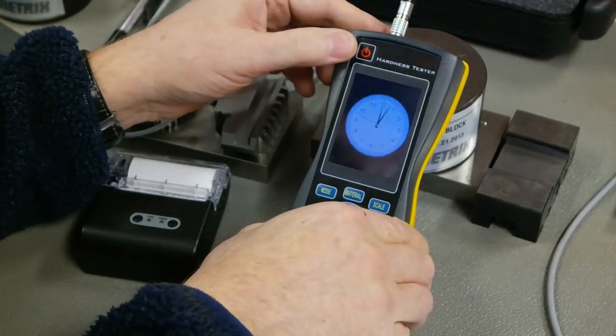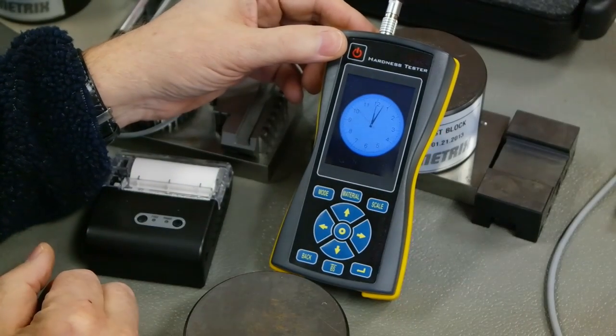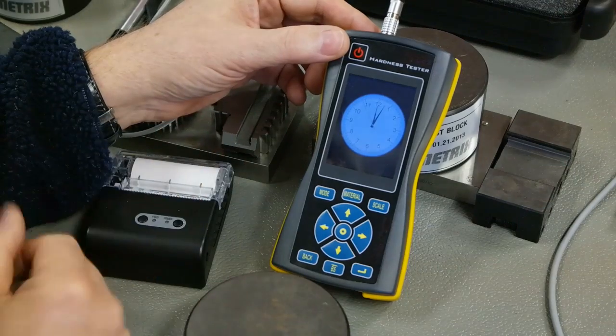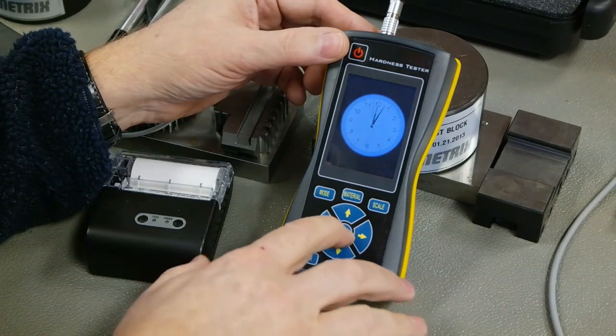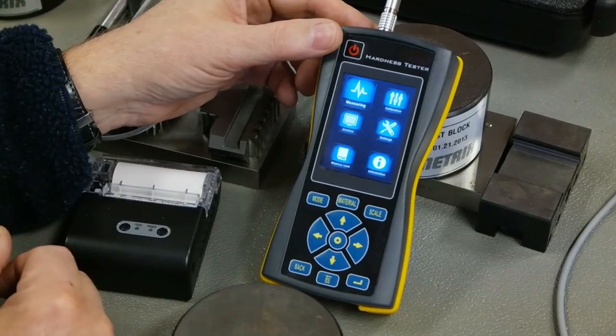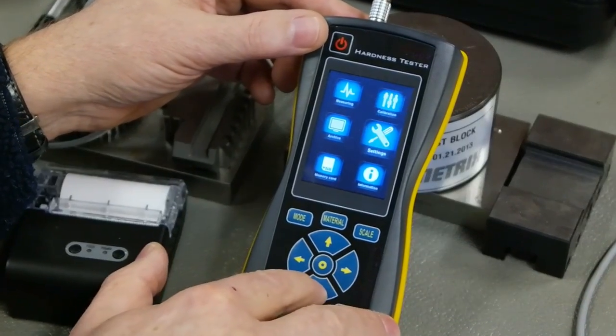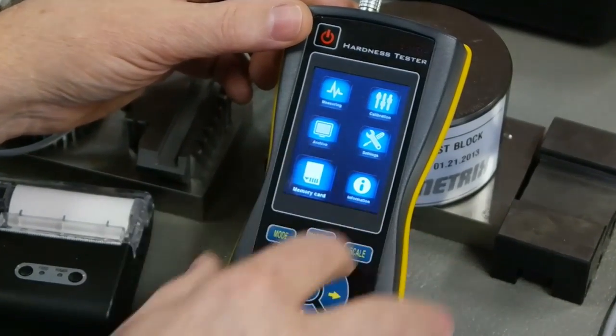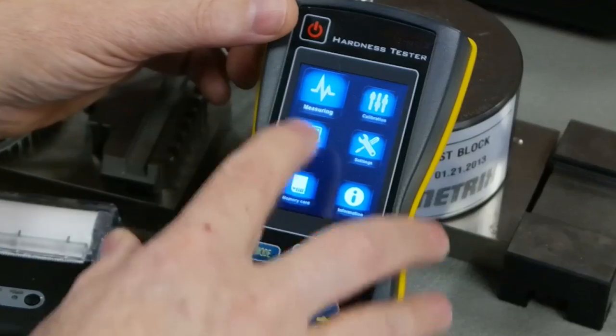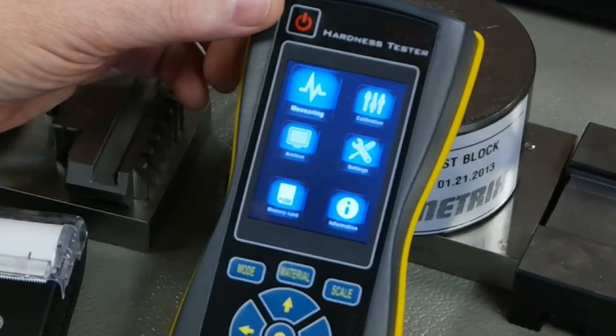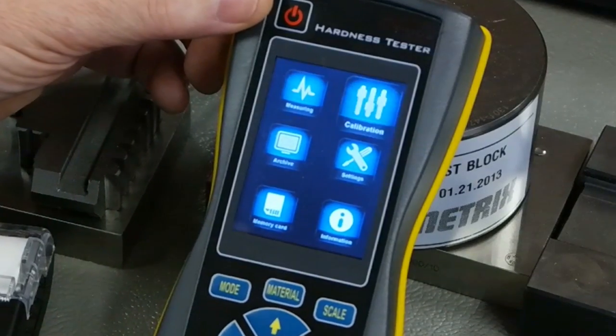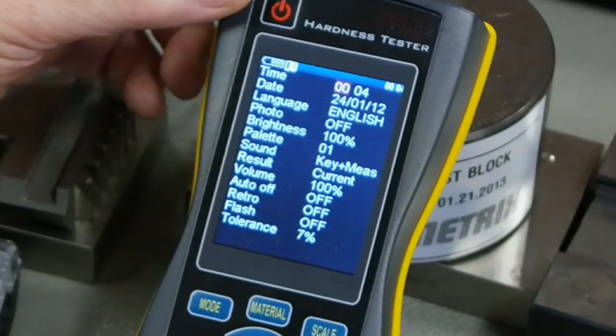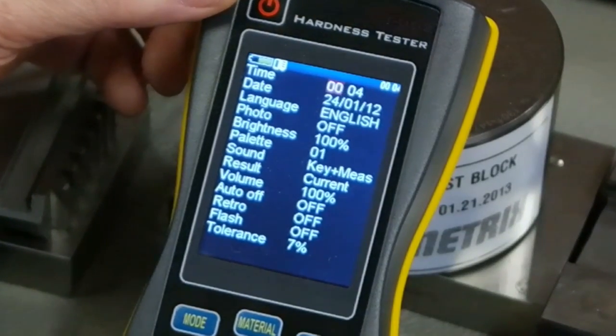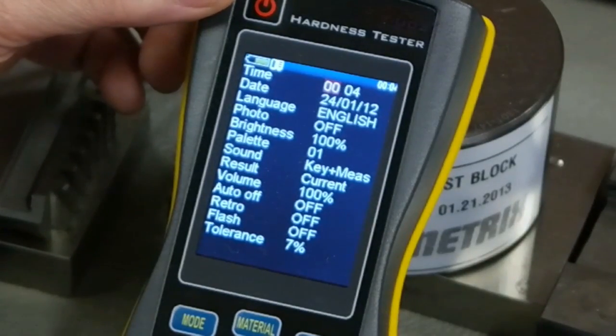And here on this device you can see that the display is showing a clock right now because it's gone into its timeout mode. The display dulls a little bit to save the batteries. So I hit any key and now the display comes alive. Clearly it's colour, and we can very quickly just move around these various parts of the display. So we have measuring, top left, then calibration. Archive is where we store the tests for upload to a PC later on, or just a review on the display. Settings is for changing the click on the keyboard when you press it. The timeout for the display to switch off, or the unit to switch off to save batteries. The brightness, all of those sort of things are available here under the user settings area.